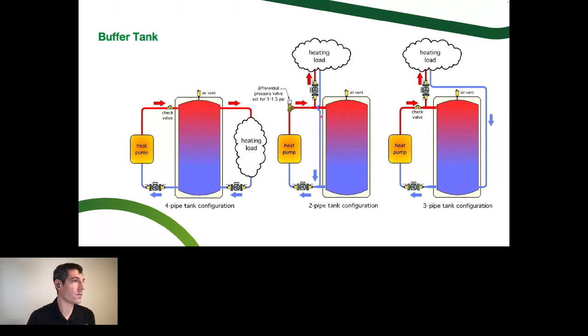So what are some other options for how we pipe these tanks? We could cap or plug the right side of the buffer tank here for a 2-pipe configuration. And in this scenario, if we turn on the heat pump and the power went out for 8 hours or something like that, so it's a design day, this ECM circulator is moving at 100% of whatever the flow rate is. In that case, the heat pump kicks on, all of that water goes right out to the building, and it comes back, and it goes right into the return of the heat pump or the boiler. In that scenario, this is just a stagnant tub of water.